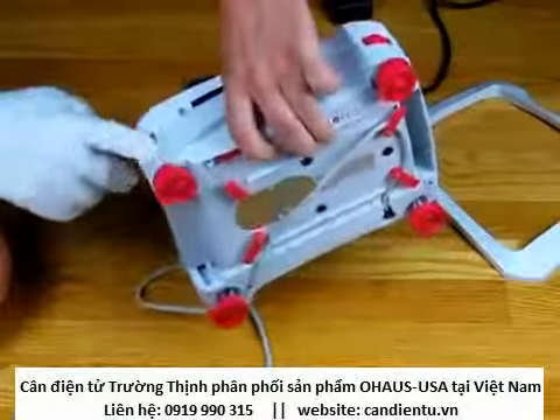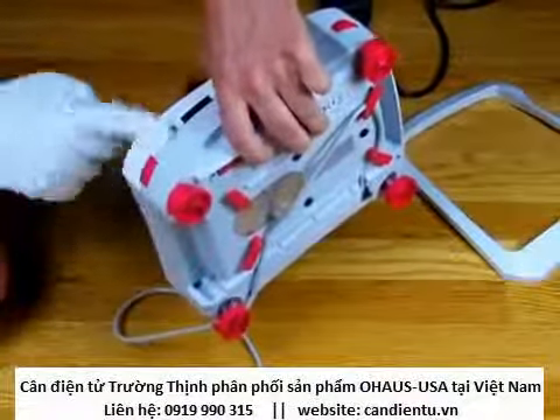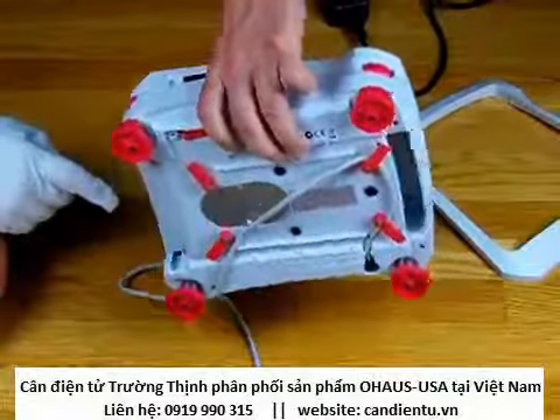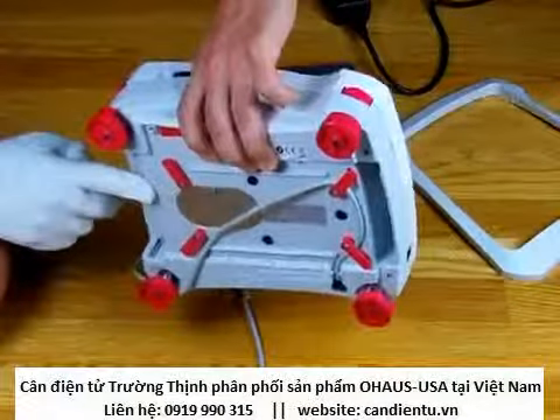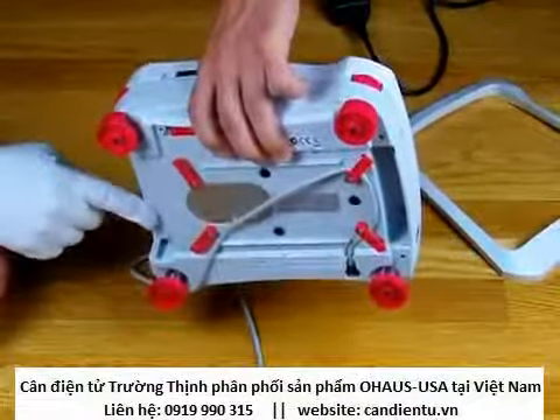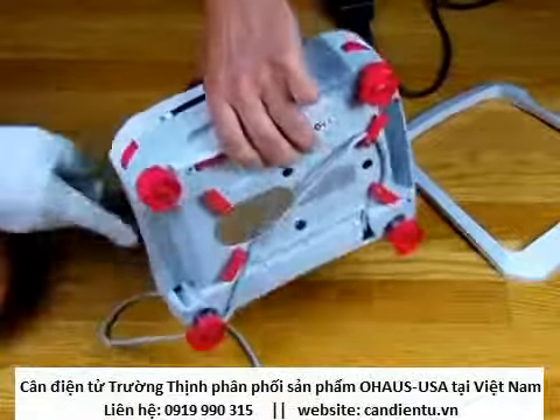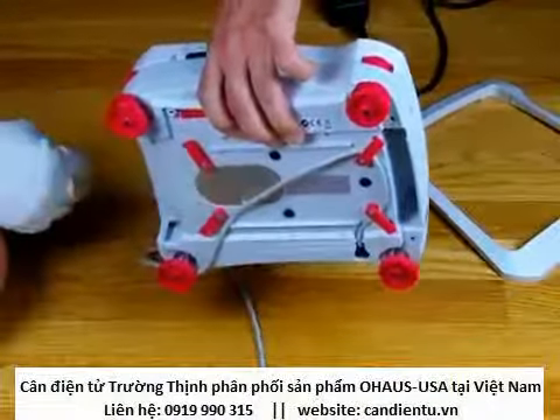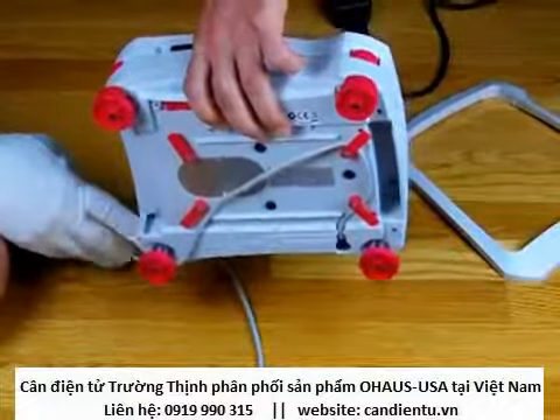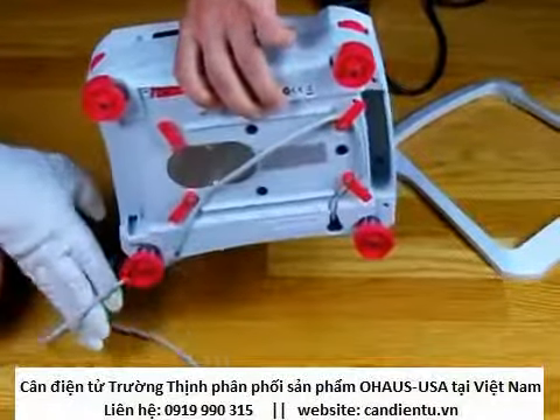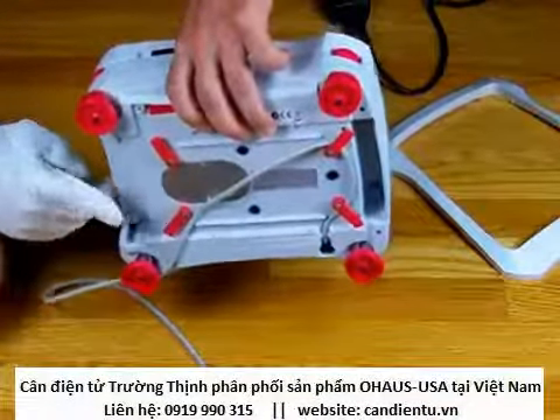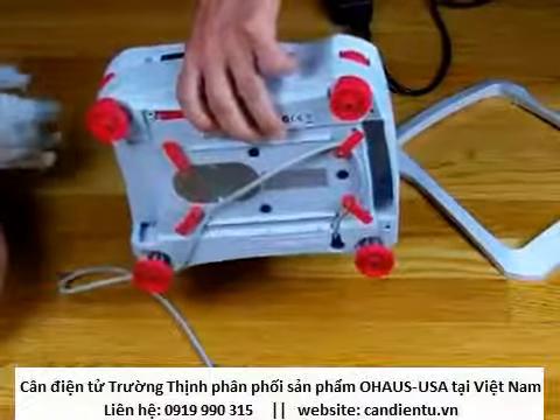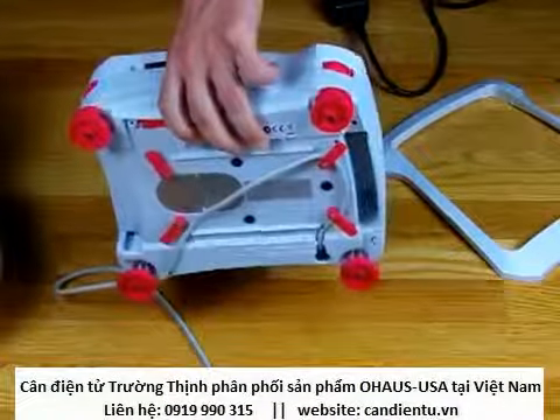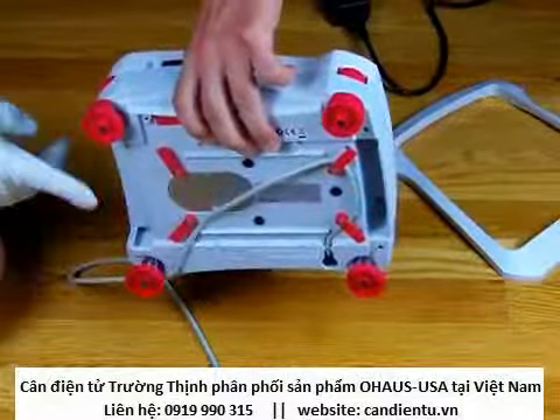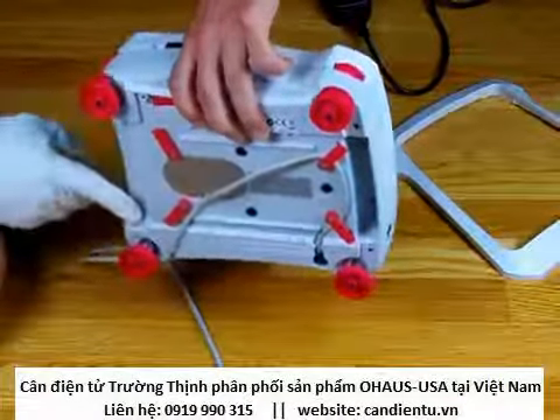We have 4 adjustable feet, adjusted by just moving this lever here. The housing itself is cast aluminum with some plastic around it, so it's nice and sturdy and gives you real good weighing results. A lot of times if it's a plastic body, it could actually flex when you're applying a load, so high quality balances will always have a cast aluminum body.